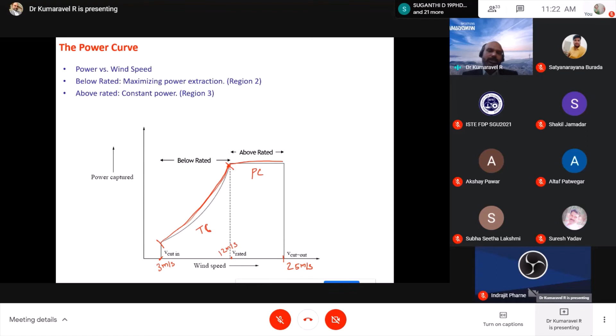So this is the pitch controller, and this portion is the torque controller. Here you try to harvest more power, and harvesting more power is nothing but harvesting more mechanical torque. So this is the torque controller that comes into the picture in this wind speed region, and beyond the rated wind speed and up to cutout is the pitch control that takes place. Both torque control and pitch control are governed by the main turbine controller.